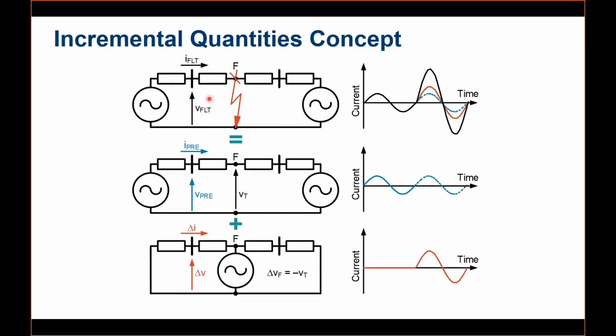The primary intention behind solving this faulted network is to divide it into 2 networks. We call the first one the pre-fault network, because the relay is measuring the pre-fault as well. So we can break that network into 2 networks: a pre-fault network, which is the healthy, normal one, and a faulted network with no source, but just a faulty source available at the point of fault. If you look at the black waveform, consider this as the waveform of the fault. The black waveform will divide into two parts. One is the blue, which is the pre-fault, or the healthy currents and voltages that were flowing before, and the other is the change.